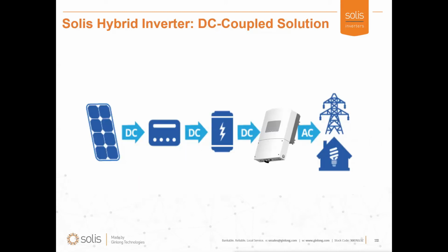The Solis hybrid inverter series is designed to work with DC coupled energy storage devices. The inverter is directly connected to the PV array, the grid, and the battery through some sort of battery management system. Sometimes this is referred to as a high voltage system, since the DC voltage going to the battery is relatively high. Compared with AC coupling, this is the more efficient method of storing and releasing solar energy.